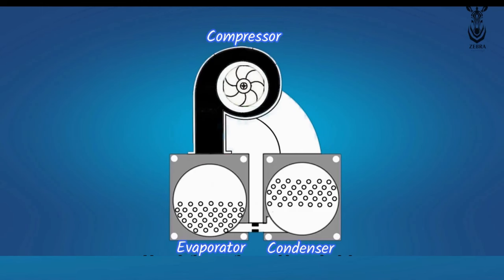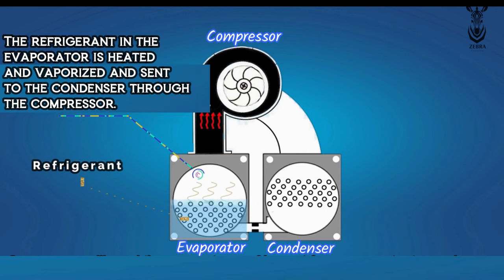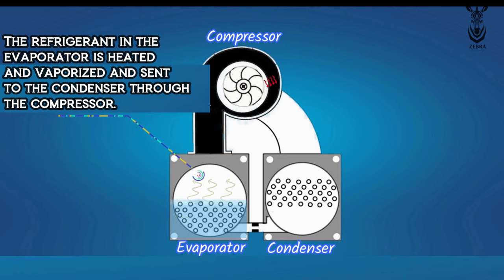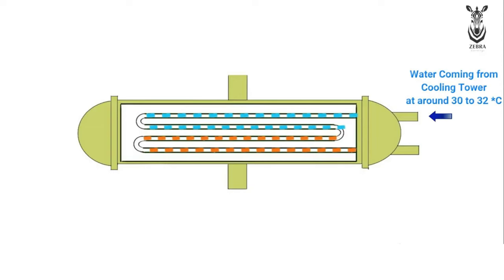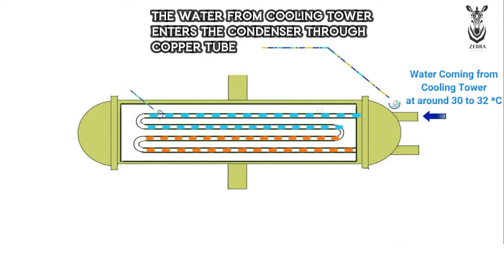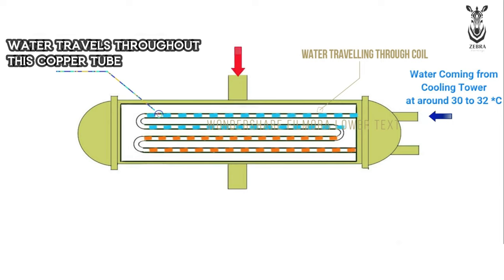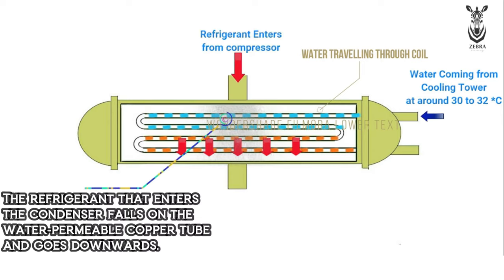Now let's see its working principle. The compressor sends the refrigerant to the condenser from the evaporator, which is in the vapor phase. The water coming from the cooling tower enters the condenser at 32 degrees Celsius through the copper tubes. This water travels throughout the tube. In the condenser, the refrigerant travels around the copper coils.